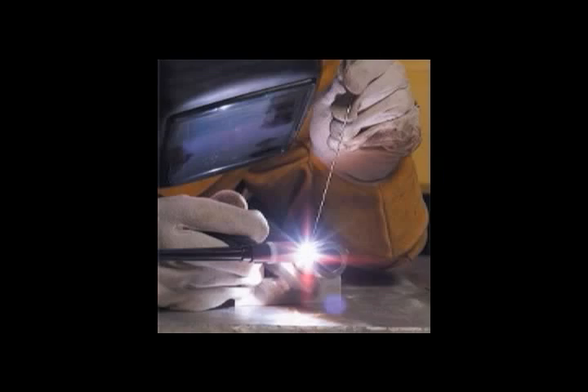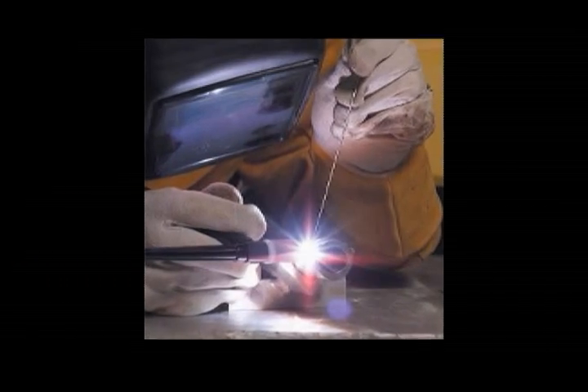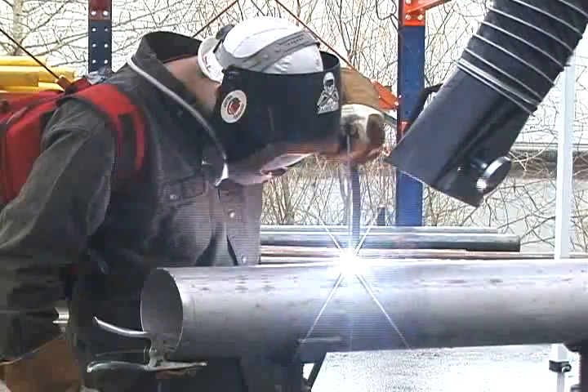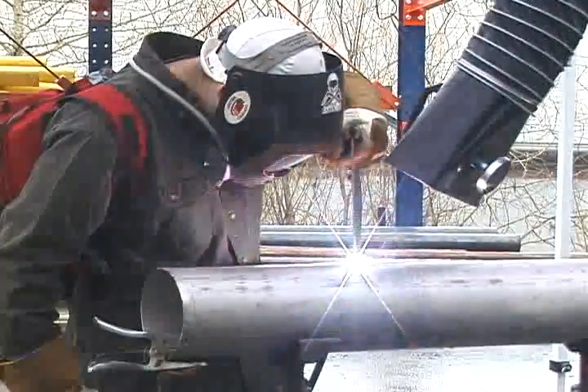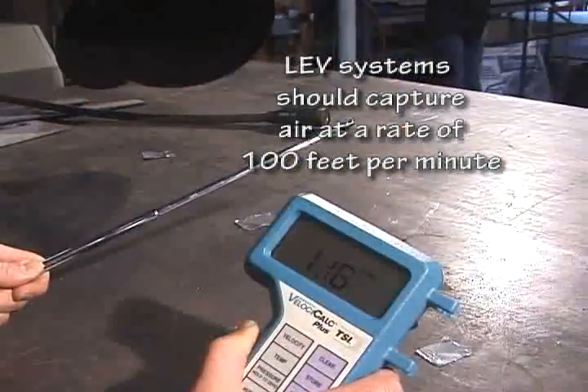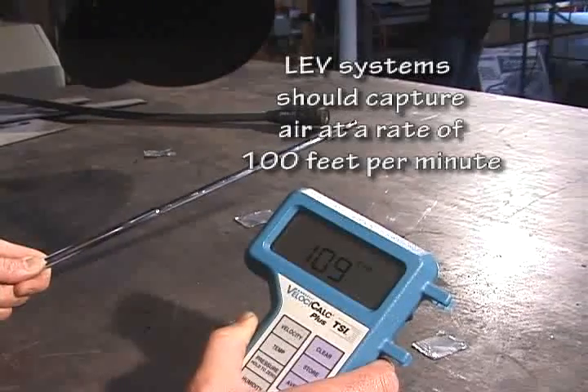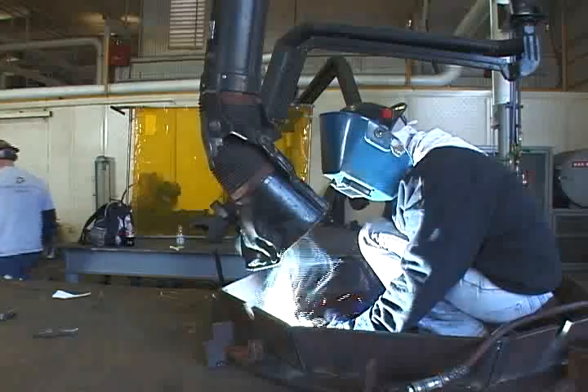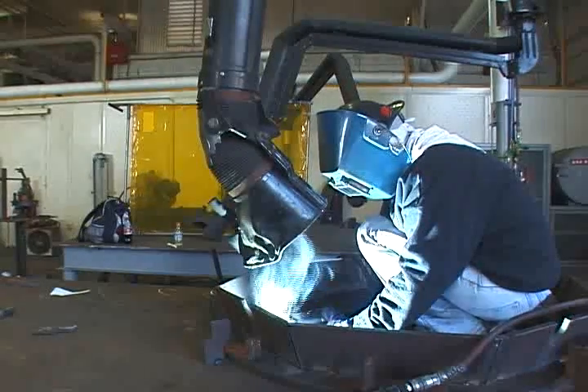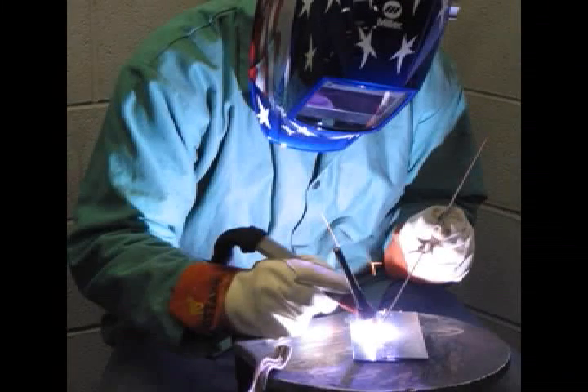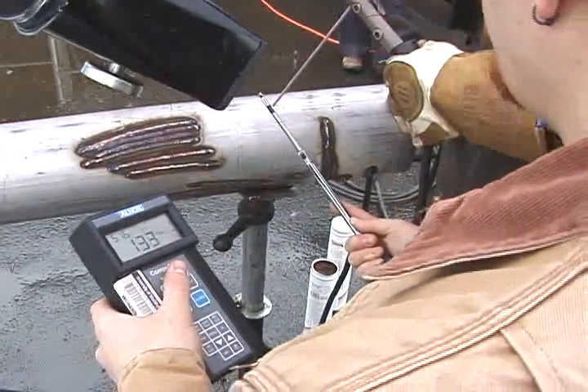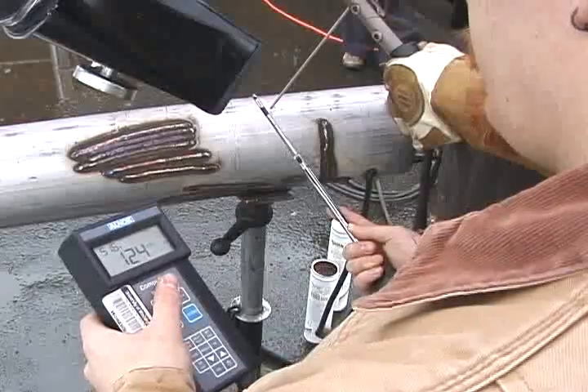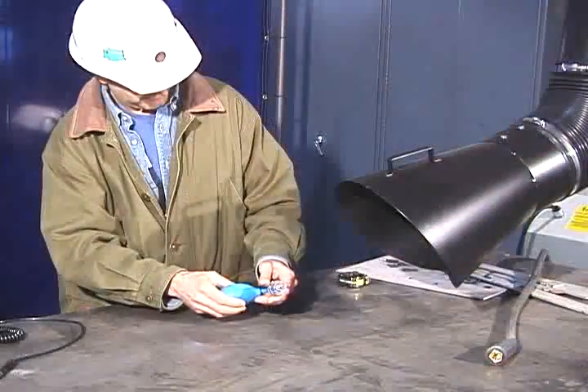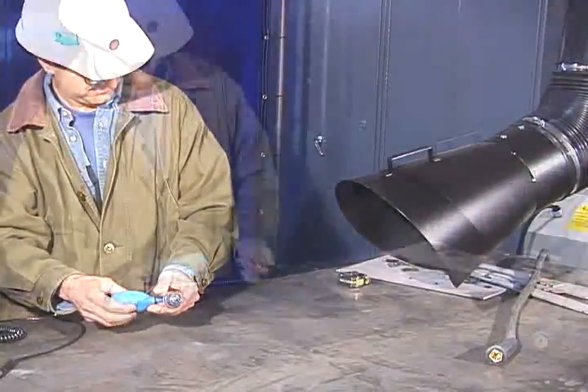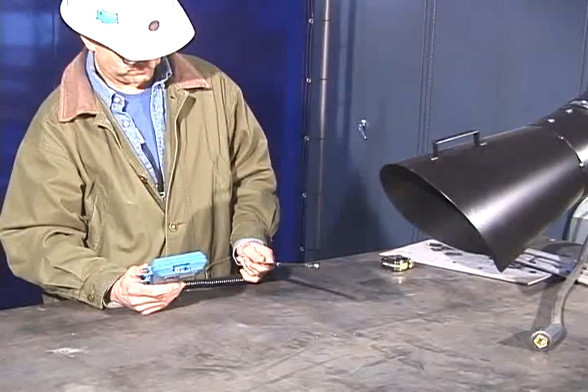Many welders are concerned that the LEV system will pull away their shielding gas. L&I specifies that an LEV system should capture air at a rate of 100 feet per minute at the source. This is known as the capture velocity. This velocity will draw the fumes away from the source without pulling the protective shielding gas away from the molten metal. Capture velocity is evaluated using a testing instrument that can measure air velocity in feet per minute. Industrial hygienists often use these instruments to evaluate the effectiveness of ventilation systems.